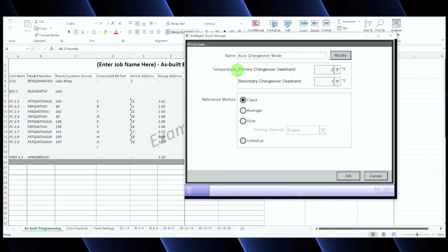And here's where we're going to go in and set up our primary changeover deadband and our secondary changeover deadband. Now, the way that this basically works is, let's say the set point was 70 degrees. I'm in auto, but the room temperature is 65 degrees. The thermostat's just going to say heat. Why? Because the thermostat is only going to say the active mode that it's in, or the current mode that it's in. The ITM is in auto, but the nav controller is only in heat or only in cooling.